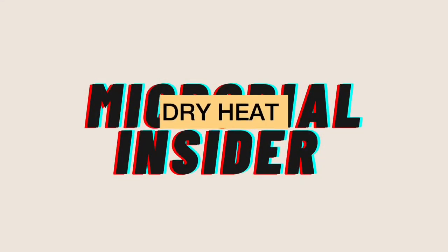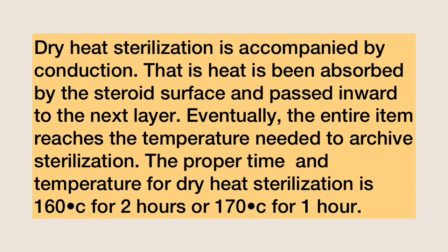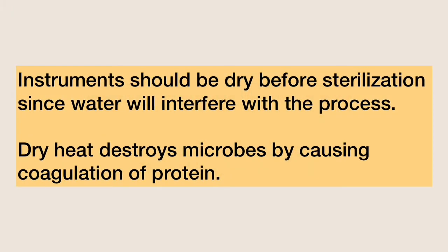Let's move on to the dry heat methods used in controlling microbial growth. Dry heat sterilization is accomplished by conduction — heat is absorbed by the outer surface and passed inward to the next layer until the entire item reaches the temperature needed for sterilization. The proper time and temperature for dry heat sterilization is 160 degrees Celsius for 2 hours, or 170 degrees Celsius for 1 hour. Instruments should be dry before sterilization, since water will interfere with the process. Dry heat destroys microbes by causing coagulation of proteins.